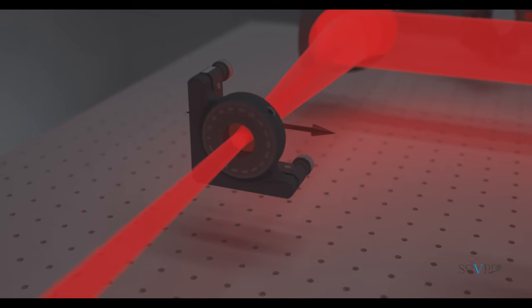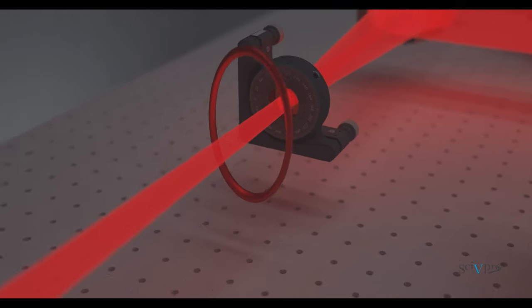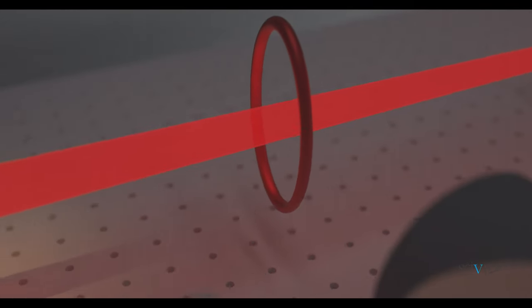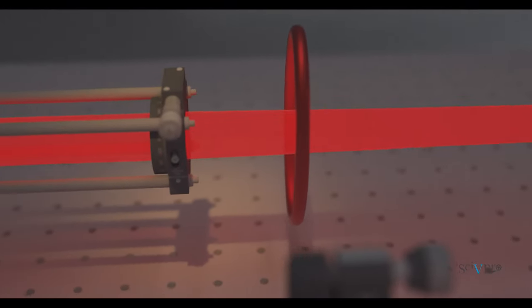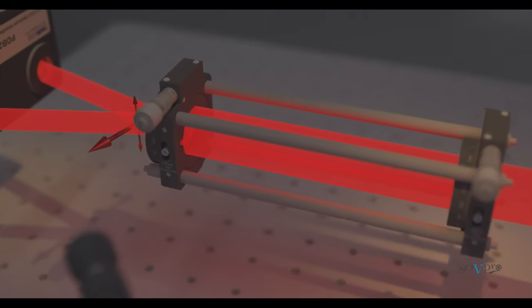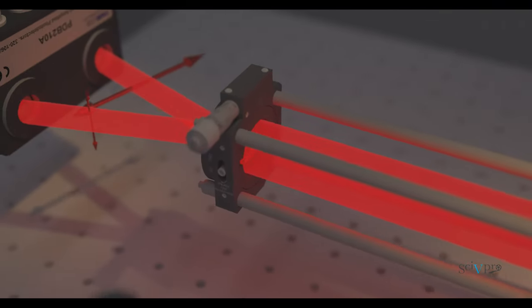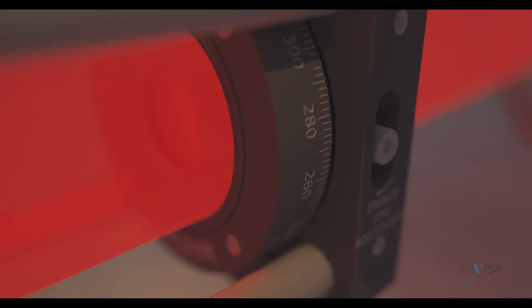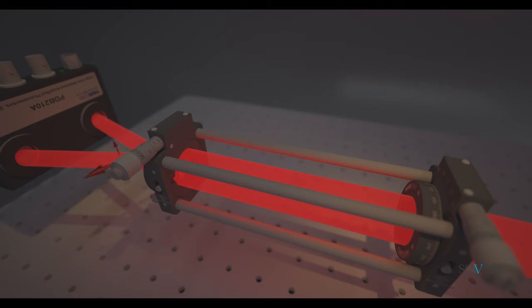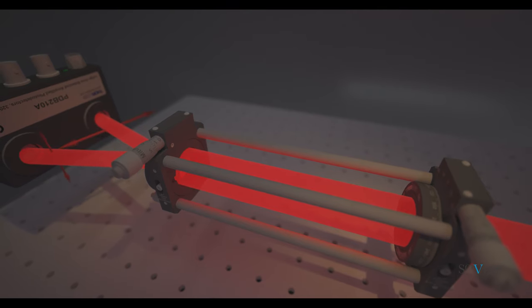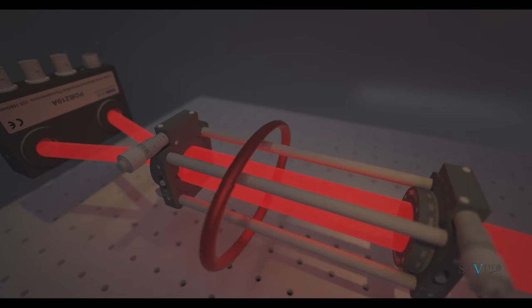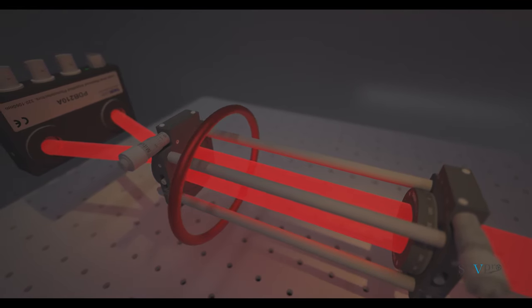Before running an actual measurement, the detection optical assembly needs to go through a calibration procedure without any terahertz signal. A probe pulse exiting the crystal without appropriate phase would result in a non-zero detector output even without any signal. The compensation procedure consists in adjusting the quarter-wave plate until the reading of the balanced photodiode is close to zero volts, or equivalently, until the probe pulse exiting the quarter-wave plate is circularly polarized.